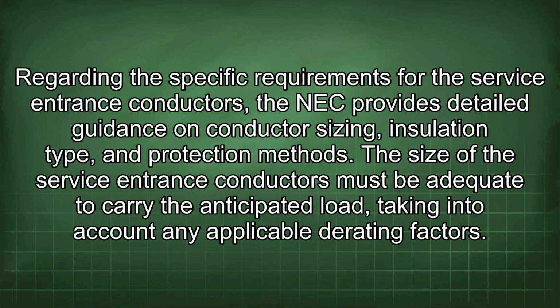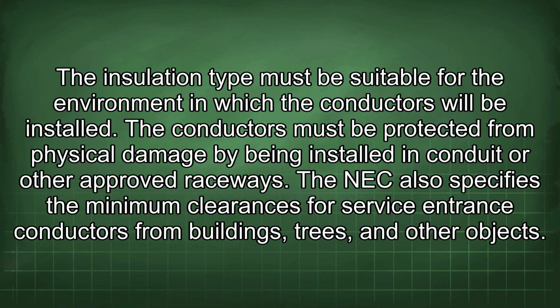Regarding the specific requirements for the service entrance conductors, the NEC provides detailed guidance on conductor sizing, insulation type, and protection methods. The size of the service entrance conductors must be adequate to carry the anticipated load, taking into account any applicable derating factors. The insulation type must be suitable for the environment in which the conductors will be installed. The conductors must be protected from physical damage by being installed in conduit or other approved raceways. The NEC also specifies the minimum clearances for service entrance conductors from buildings, trees, and other objects.